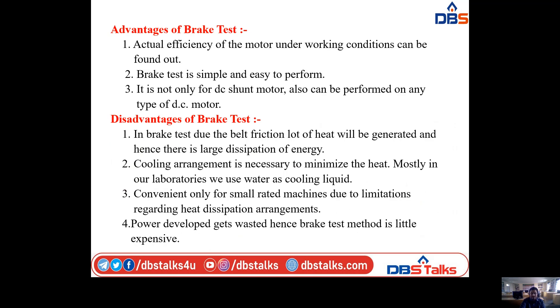Advantages of brake test: The actual efficiency of the motor under working conditions can be found. The test is simple and easy to perform because the load is applied directly. It can be performed on any type of DC motor, not only the DC shunt motor.